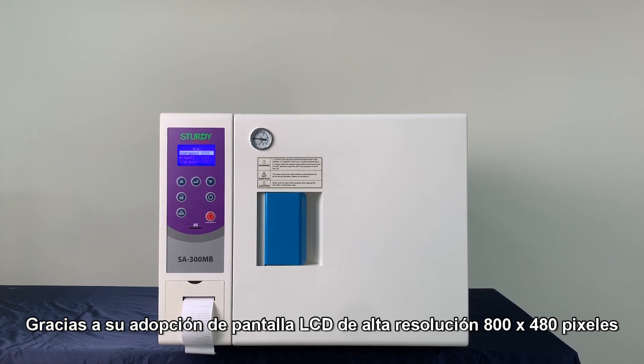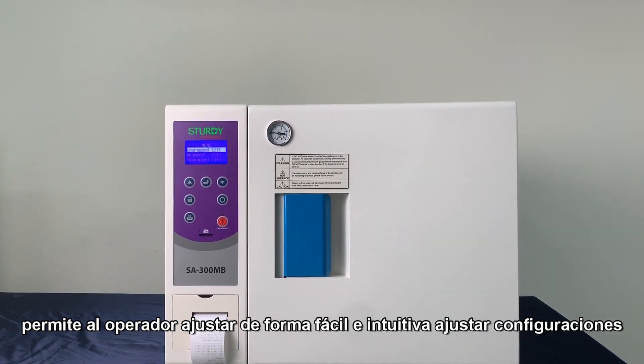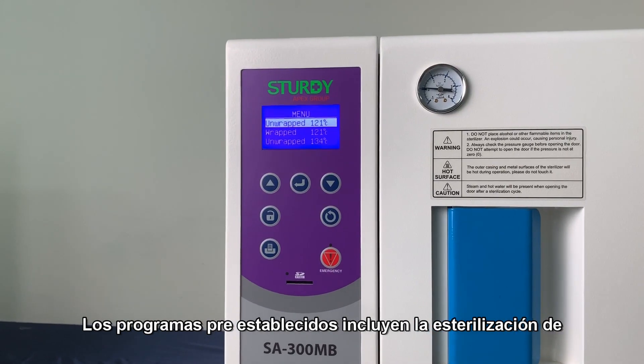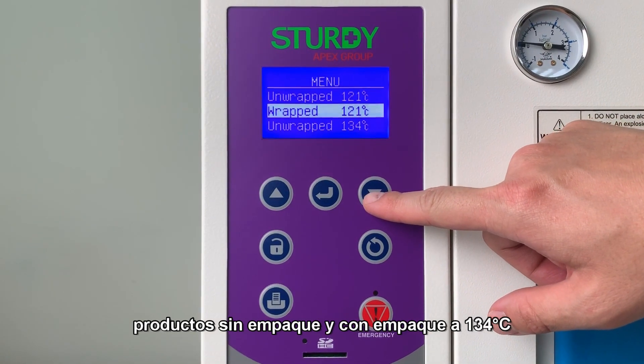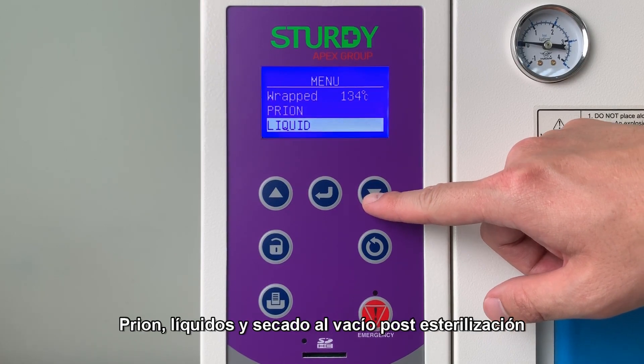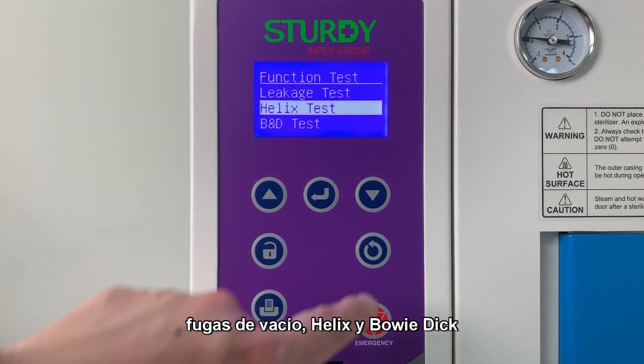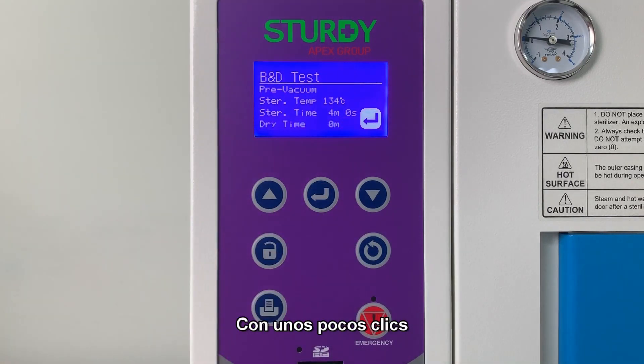Let us take a look at the control panel. Thanks to its high-resolution 800 by 480 pixel LCD display, the operator can easily and intuitively adjust settings and initiate pre-established programs with just a few clicks. Pre-established programs include sterilization of unwrapped and wrapped products at 121°C, unwrapped and wrapped products at 134°C, PRION, liquid, post-sterilization vacuum drying, and performance assurance testing including vacuum leakage, Helix, and Bowie-Dick tests.